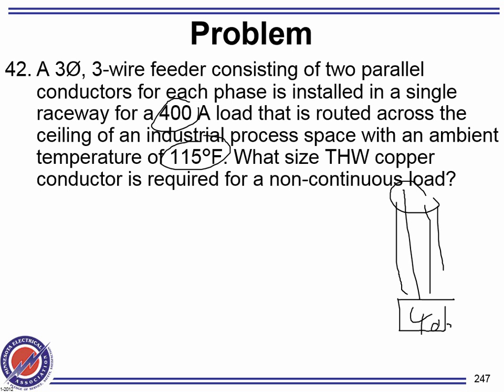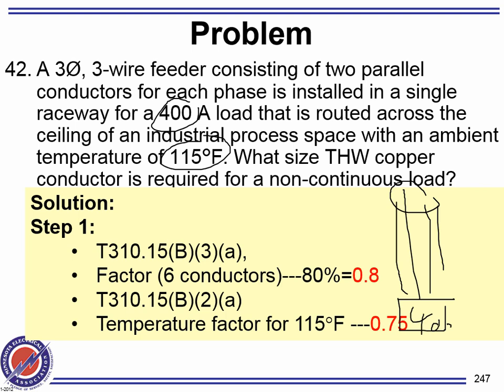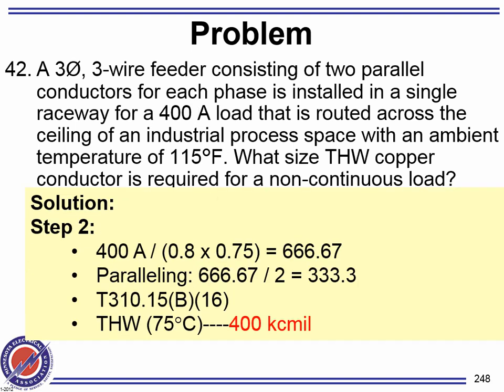But then the problem is if there's no temperature correction, guys, what would you do? You take the 400, divide it by 2, because we're paralleling two sets, and then go to 310.16 under which column? 75-degree column. Why? Because the installation is 75. And what else? I need another thing. Yes, the equipment is over 100 amp, and you're done. That's if you were not derating. Am I making sense? Because we're derating, then we have to divide by the derating. The first thing you need to do is find my derating because of bundling, and my derating because of temperature. I have to accommodate for these two. Then, gentlemen, then you divide.